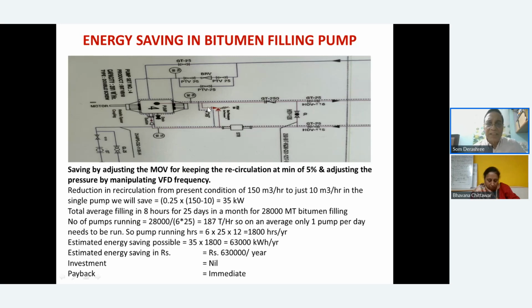And there, of course, there is a pop-up valve because it's a positive displacement pump. There is a safety valve also here. But to make sure that the safety valve doesn't pop up, they used to continue to maintain this as a recycle. Simple solution. We said, let's have a VFD here, which is now back pressure sensed. So it senses the back pressure.